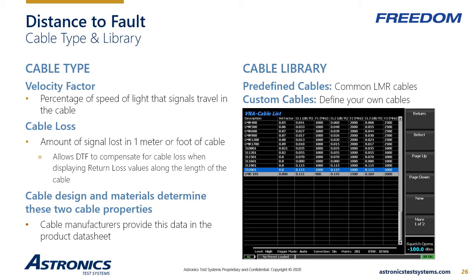Both velocity factor and cable loss are a function of the materials and design of the cable and can be found in the cable manufacturer's datasheet. However, for the user's convenience, the FREEDOM R8200 provides a library of commonly used LMR cable types. The user can also add cable definitions to this library.